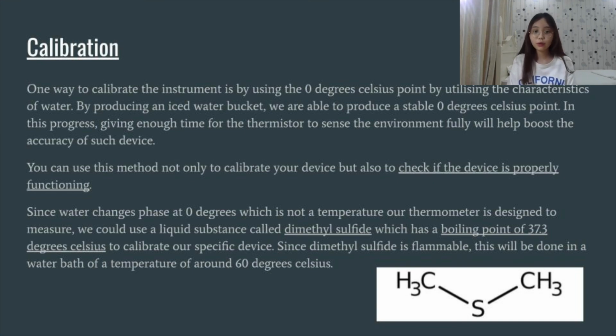Calibration: one way to calibrate the instrument is by using the 0 degrees Celsius point, utilizing the characteristics of water. By producing an iced water bucket, we are able to produce a stable 0 degrees Celsius point. In this process, giving enough time for the thermistor to sense the environment fully will help boost the accuracy of such a device.